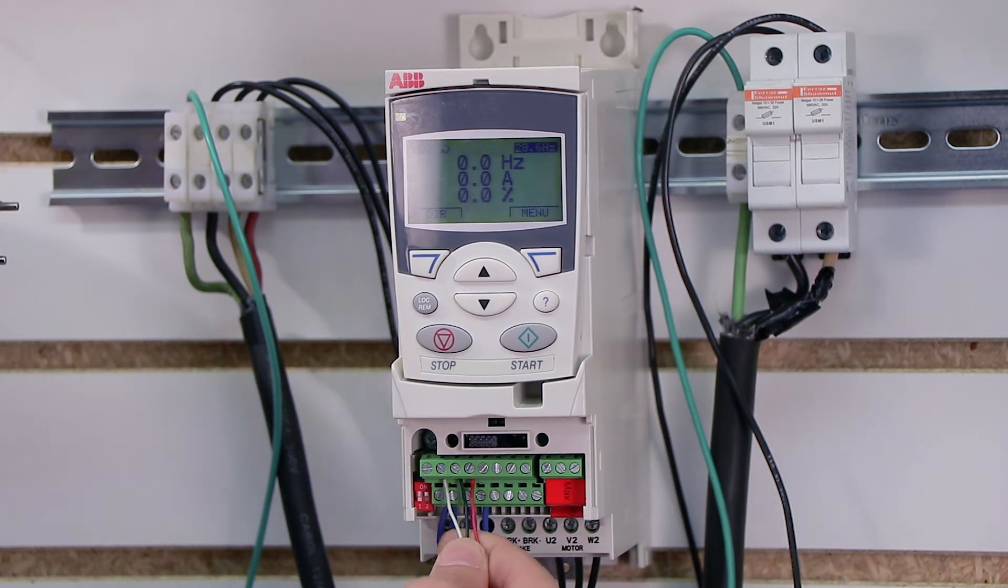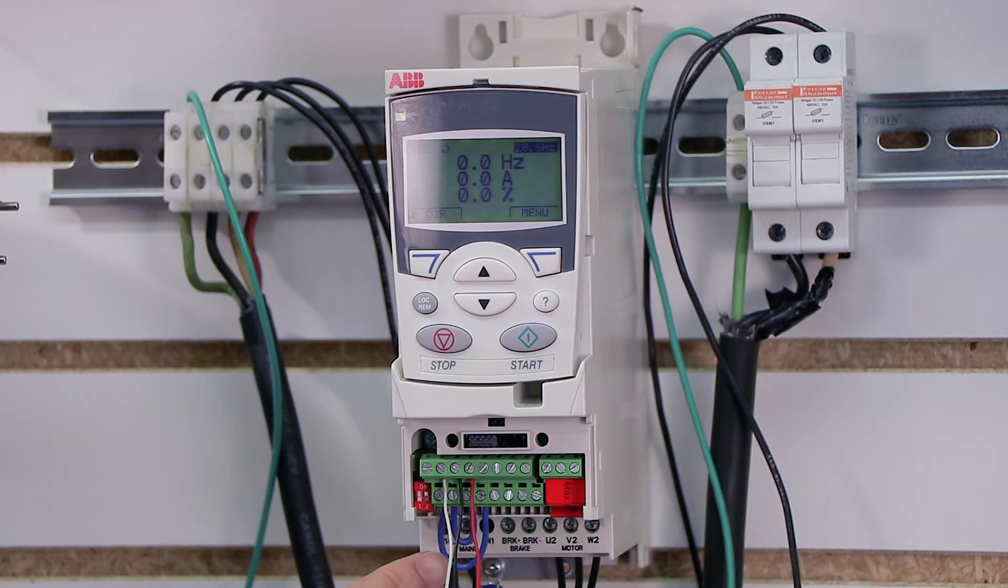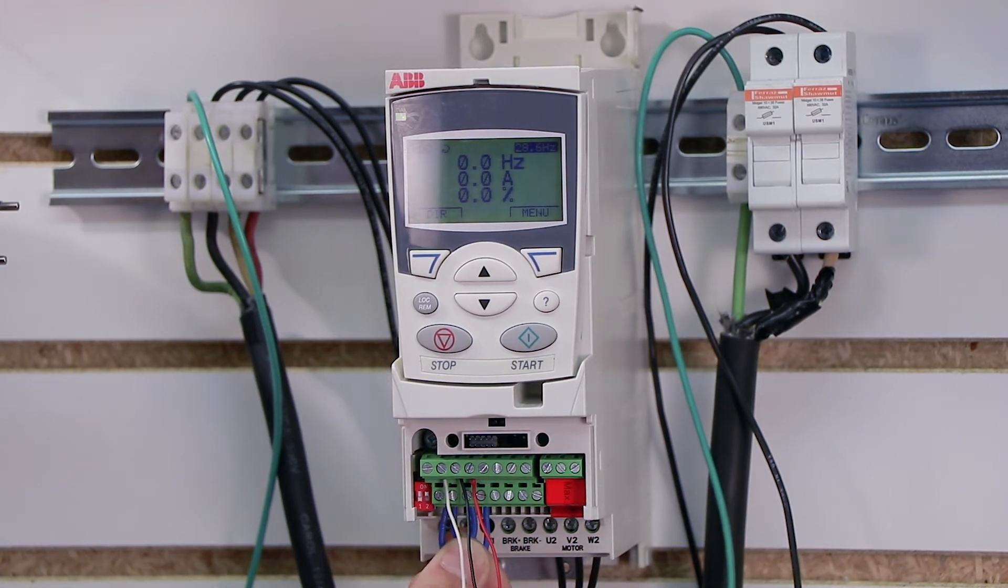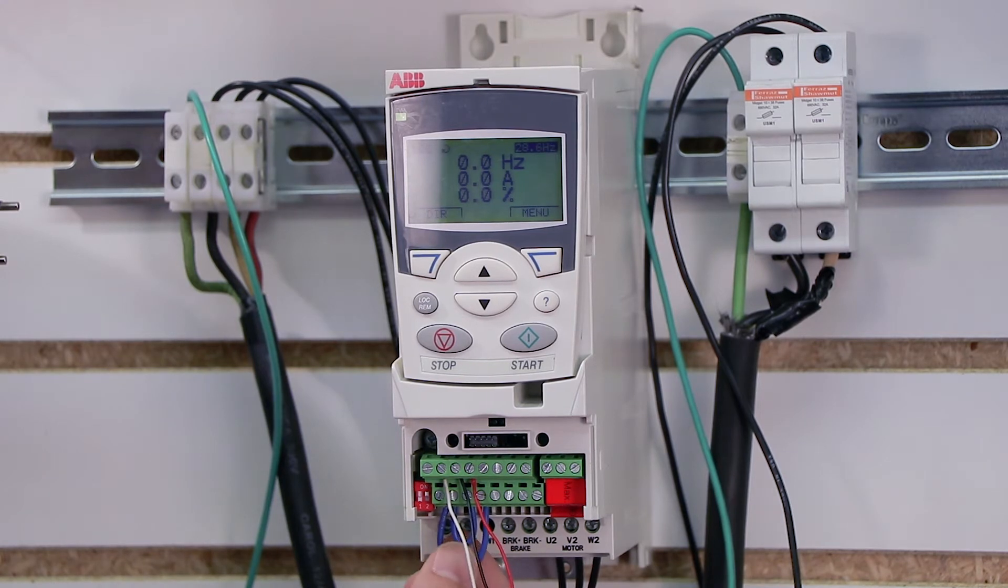But there's one more important thing we need to point out here. Notice down here I have some jumpers set up. This is because when you put the drive in speed pot control, you have to give the drive a start command of some kind. So in order for me to use the speed pot, you're going to see this a little later in the video, we need to have some kind of a start command. Now for the simplicity of this video, I did not wire an external start command or a selector switch - that's going to be in the next video.